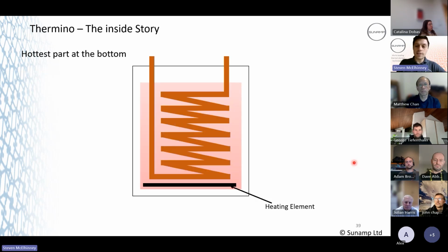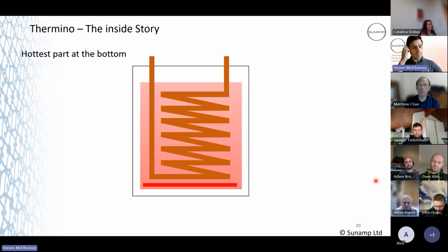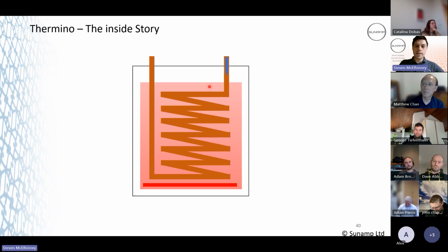Speaking of which, here we go. Heating element comes on. We charge from the bottom up, bottom to top. That temperature sensor string, we've got a bottom, a middle, and a top. The bottom one's going to heat up first, and that's where you get that off cycling, off and on, until that heat starts getting to the middle, and then the element will stay on fully.